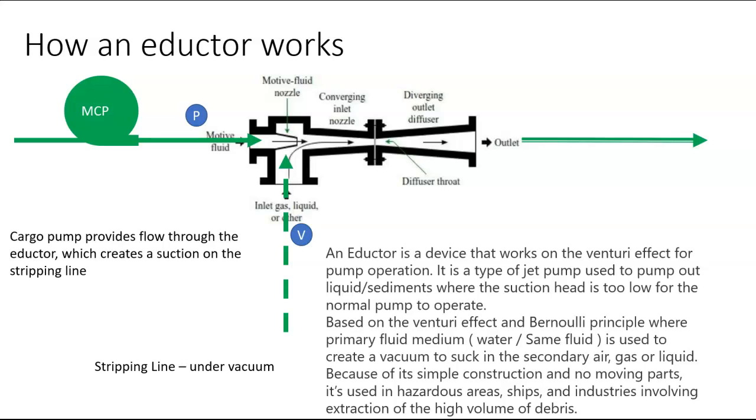But when you start running out of product and you start getting a combination of air and liquid through there, you get this kind of bubbly effect, and the pump just hates it. We're going to find out that pumps really don't like air at all. So what this allows us to do is keep the pump happy. It is discharging cargo at the same time. We're still moving cargo out of there, but it also provides a nice little vacuum source for, let's say, the emptier tank.